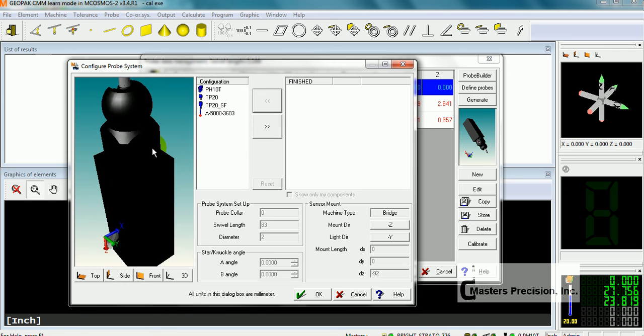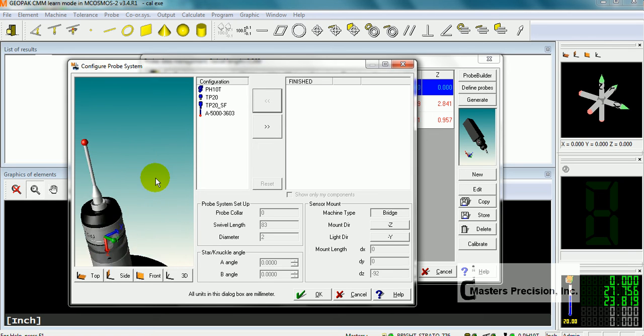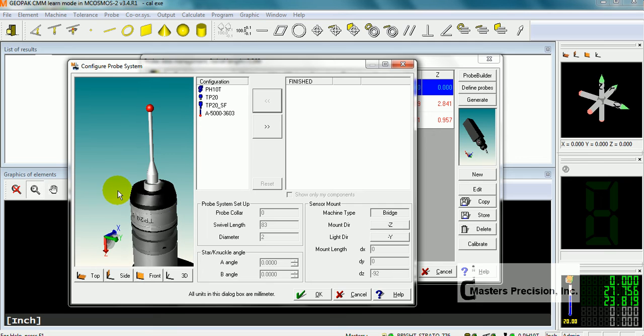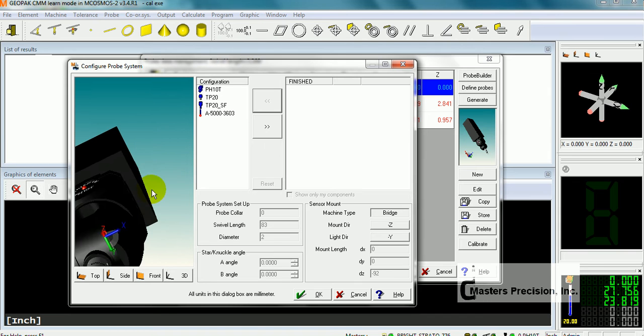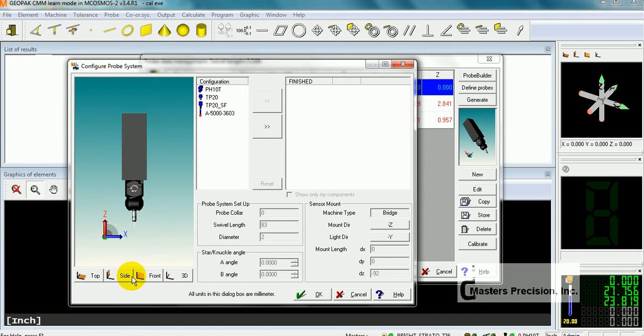Now, when you're taking the measurement, it's going to be from the base where it threads in to the center of that ruby that is your overall length. And if you have extensions, make sure you put them in there. The other measurement is going to be the ruby size itself. So just get a pair of calipers out, and if you have a special disc or a barrel, try and match it up. So we are done with this, and you can change it to 3D, front, top, and side view in this window. So we're done building our probe.